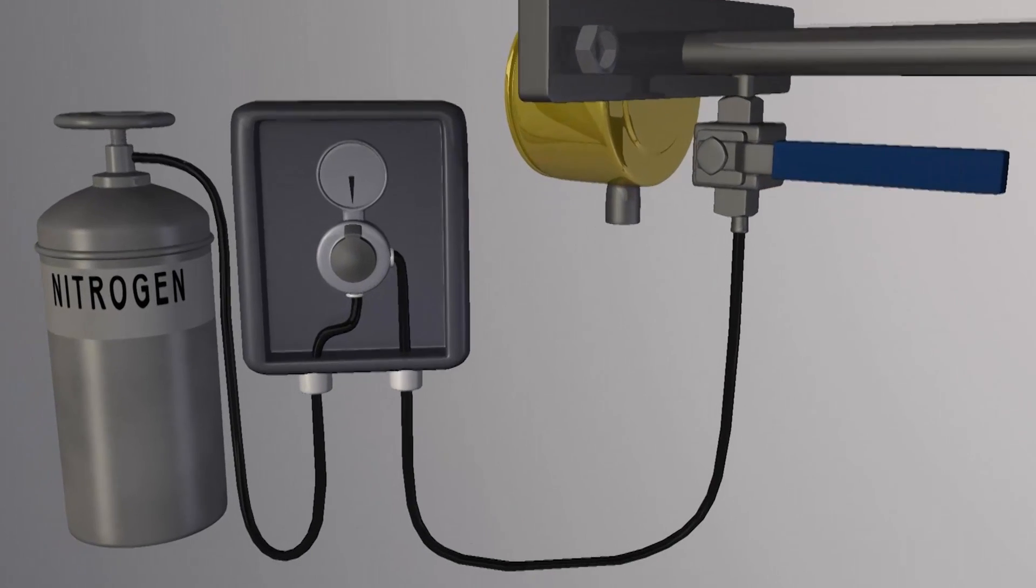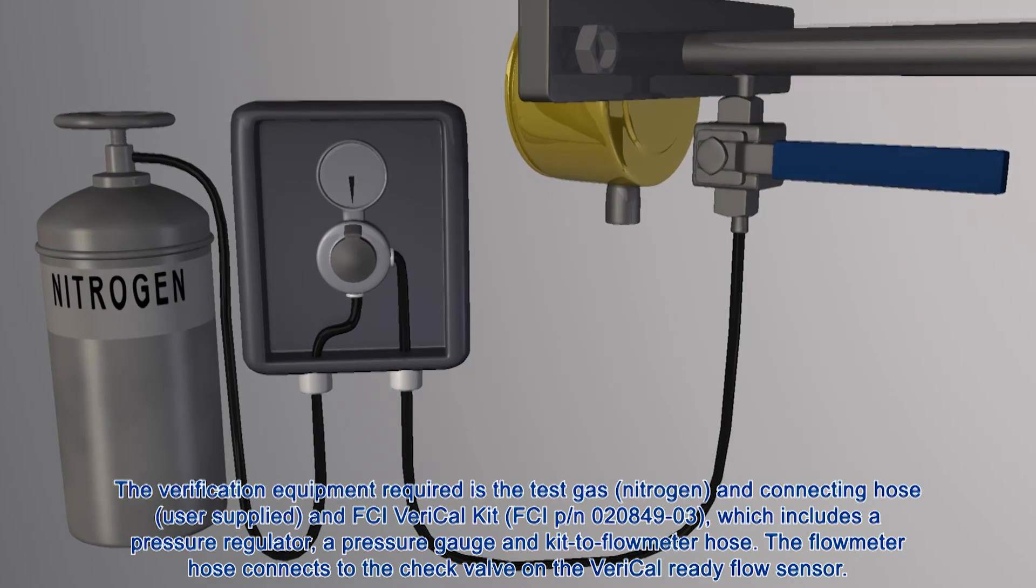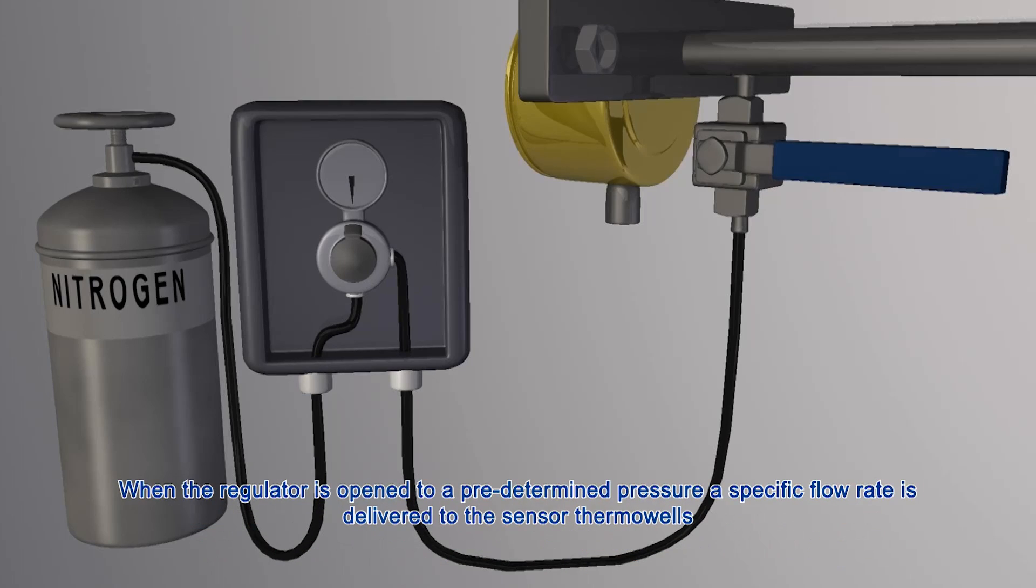The verification equipment required is the test gas, nitrogen, and the connecting hose, which is user supplied, and FCI's VeriCal kit. The kit includes a pressure regulator, a digital pressure display, and a hose connecting the meter to the VeriCal kit.